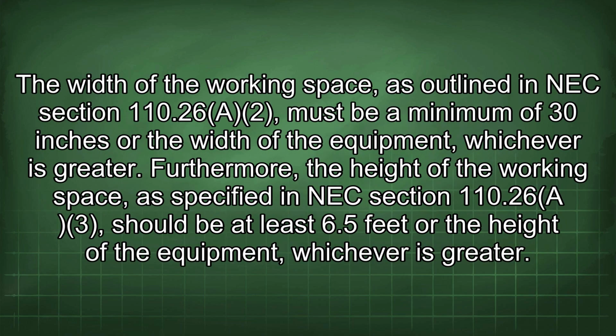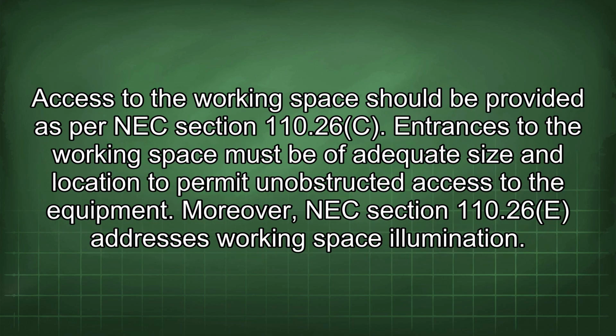The width of the working space, as outlined in NEC Section 110.26(A)(2), must be a minimum of 30 inches or the width of the equipment, whichever is greater. Furthermore, the height of the working space, as specified in NEC Section 110.26(A)(3), should be at least 6.5 feet or the height of the equipment, whichever is greater. Access to the working space should be provided as per NEC Section 110.26(C). Entrances to the working space must be of adequate size and location to permit unobstructed access to the equipment.